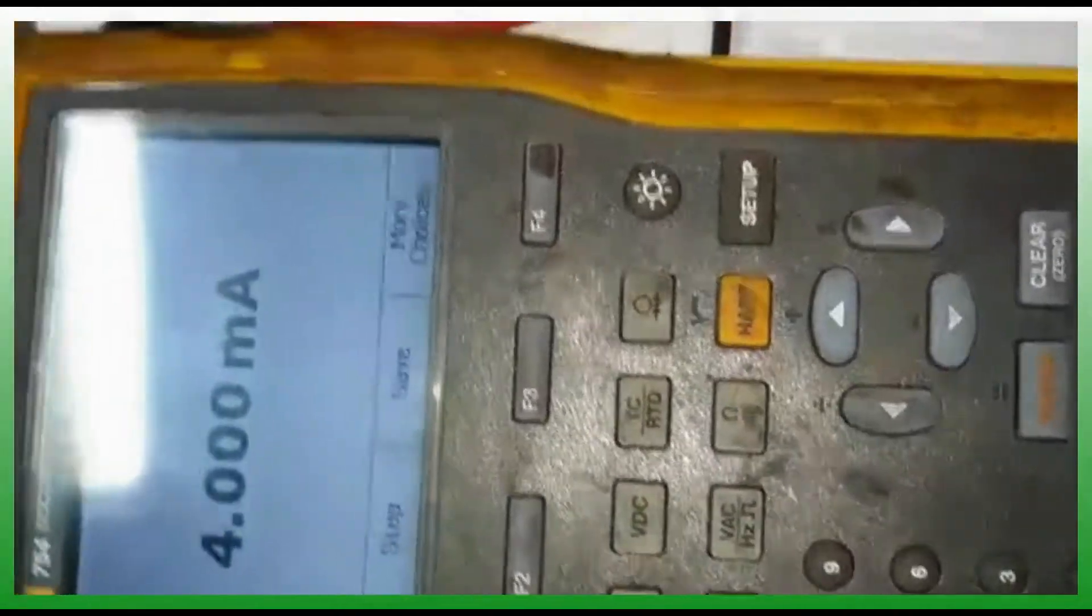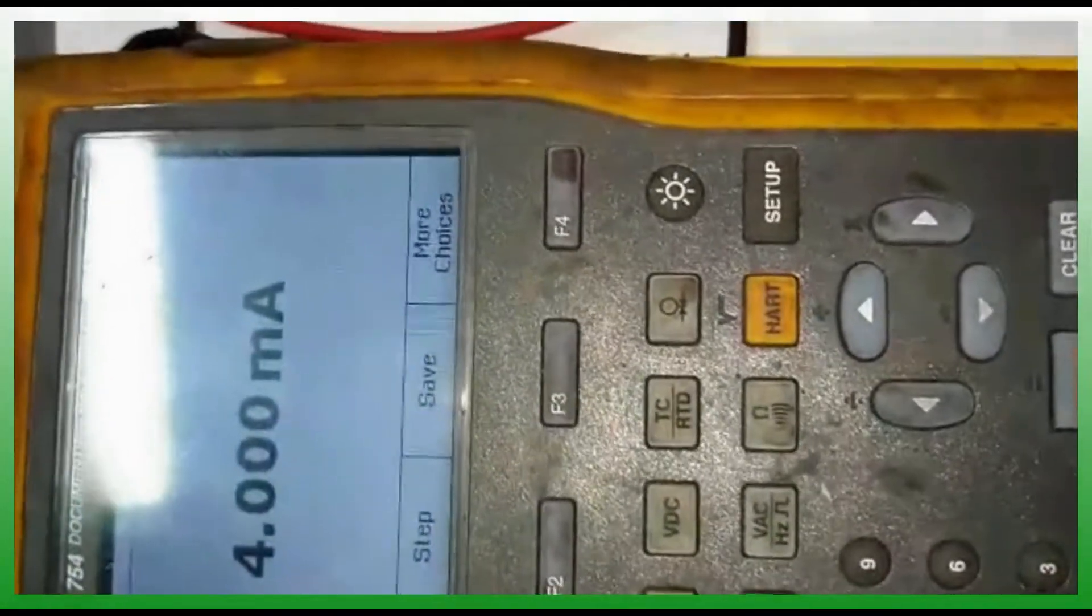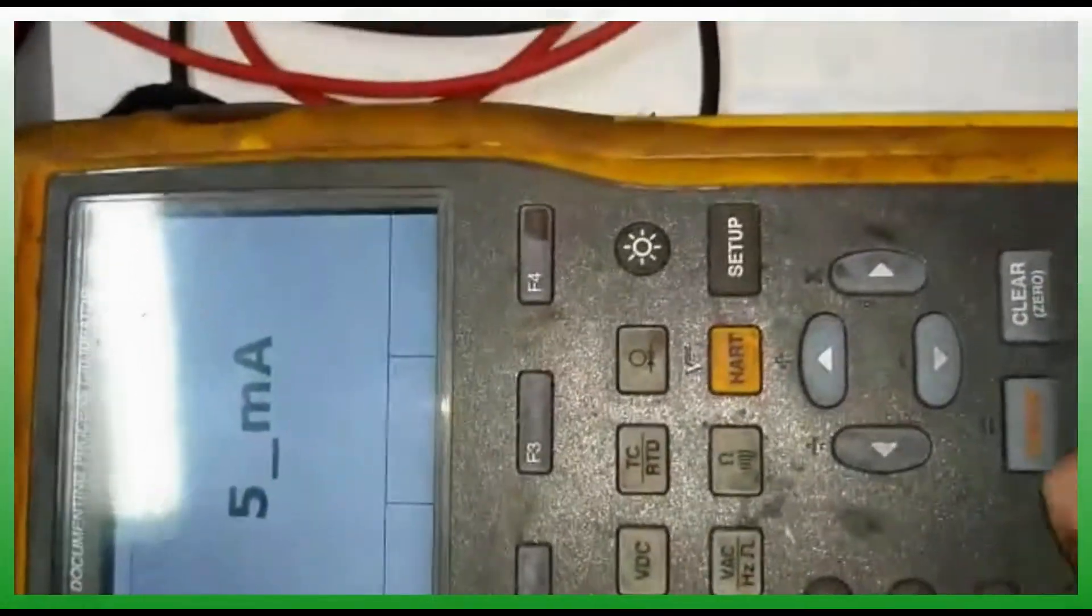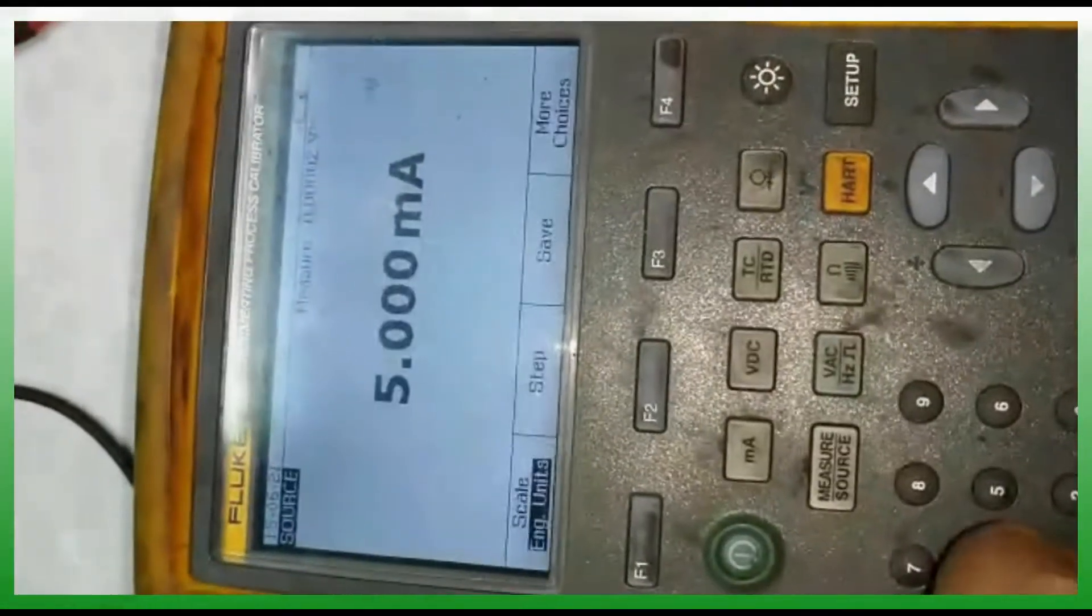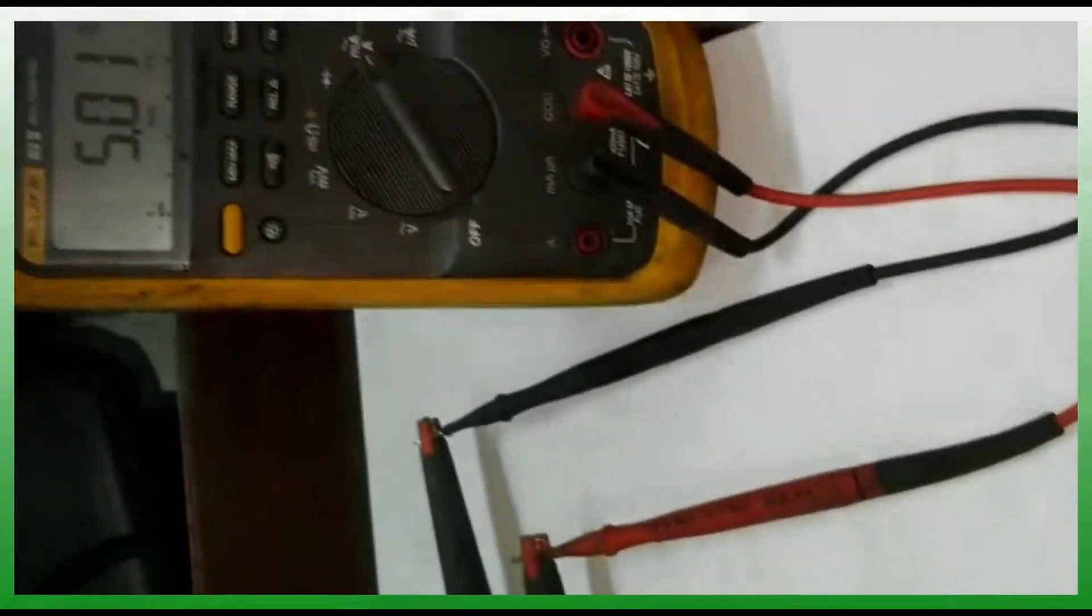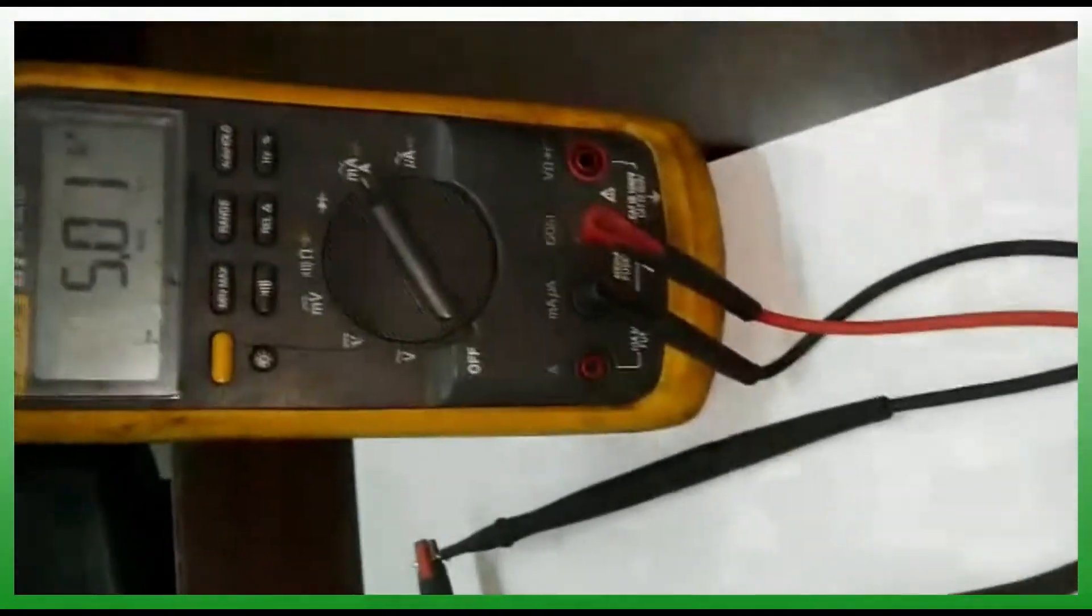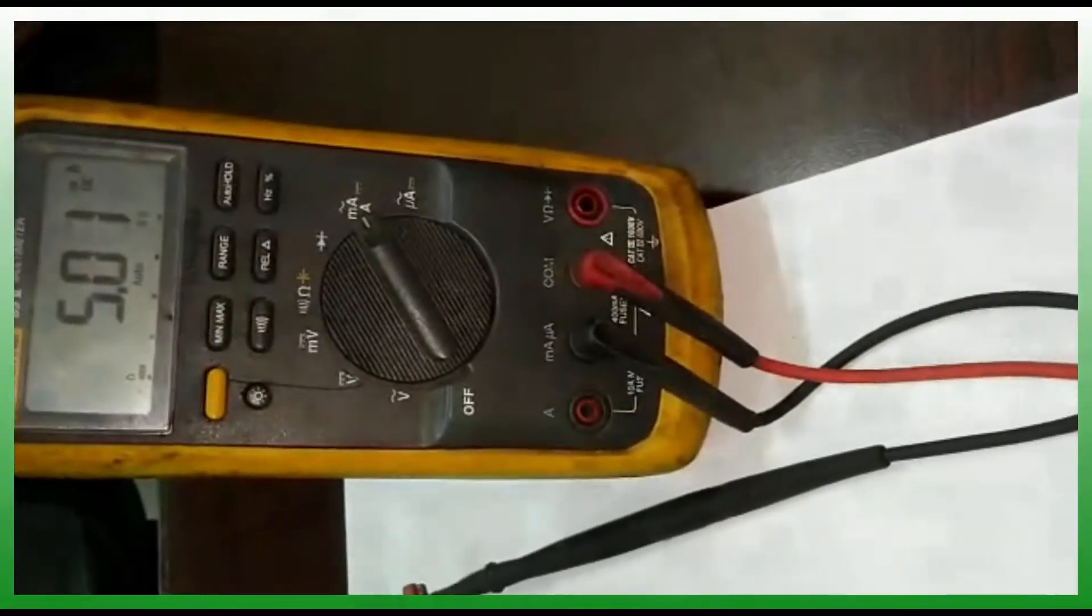In this way, the same thing will go to the I-to-P converter or your control valve. Now I'm giving the next 5 milliamps, 6 milliamps like that. I want 4, 8, 12 for the calibration.